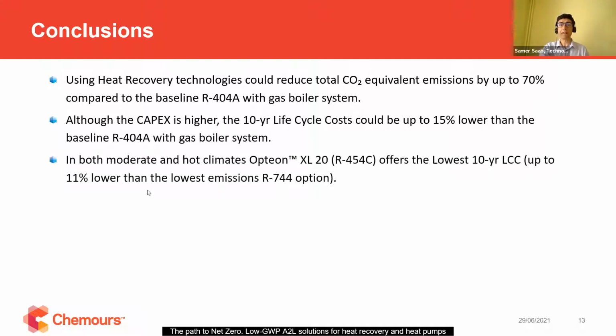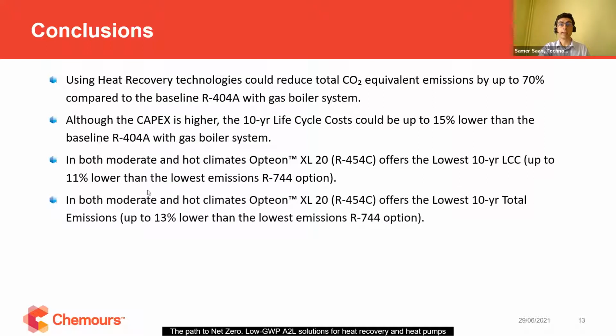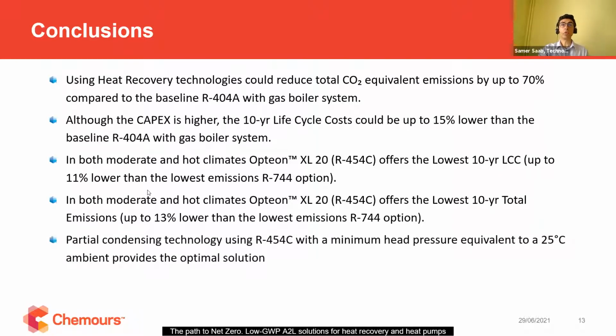In both hot and moderate climates, XL20 offers the lowest 10-year life cycle cost, down to 11% lower compared to the CO2 option. It also offers the lowest 10-year emissions, on average at minimum 13% lower compared to CO2. The best technology we saw in this study was partial condensation using XL20 with a minimum head pressure equivalent to a 25 degrees C ambient temperature.